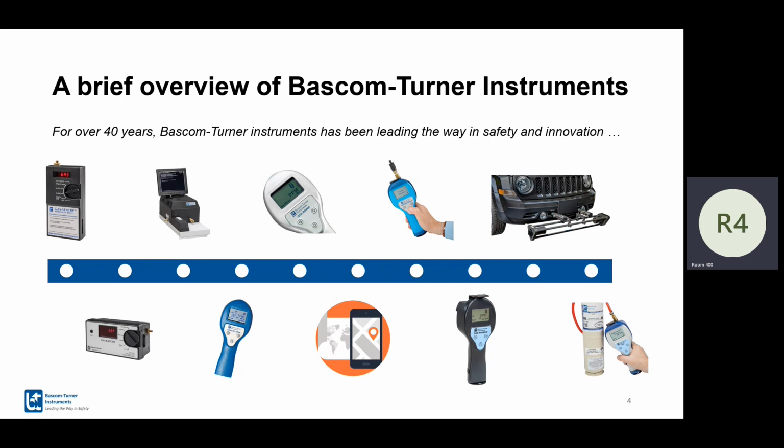In the mid 90s, we came out with our very first calibration docking station. We built this in partnership with Southwest Gas. One of the issues that they were trying to solve is how do we make calibration easier? How can we make our calibration records easier? So we worked with them, and we now have over 1,000 docking stations out with all of our primary utility customers that help with not just calibrating machines, but record keeping, and when the utility commission comes to town, they're ready to go and can pull off these units and look at their calibration records.